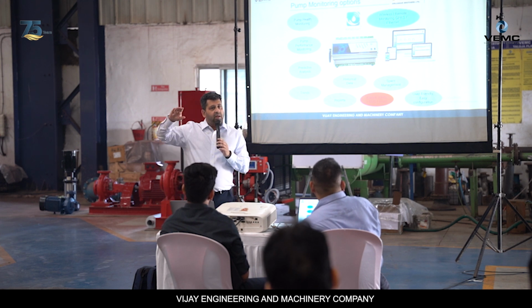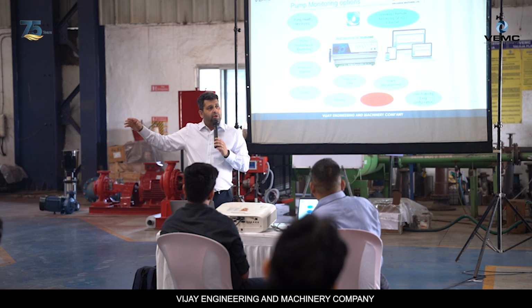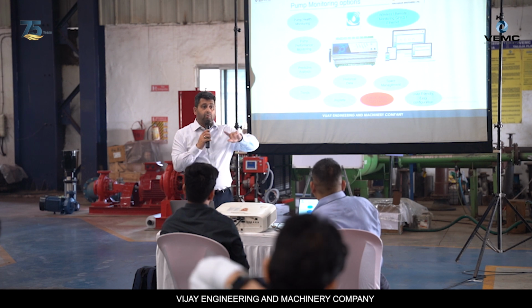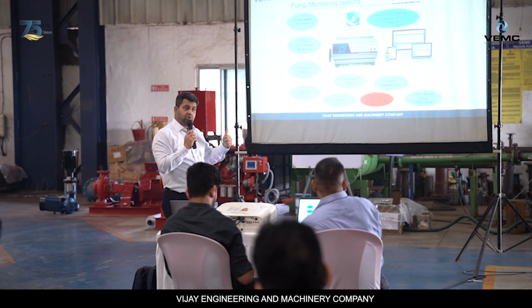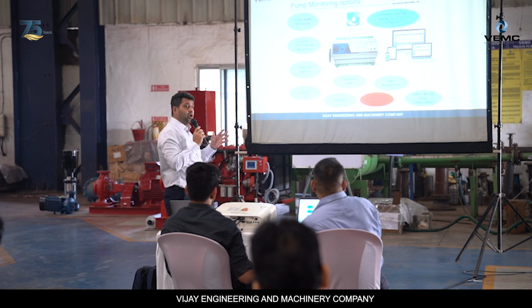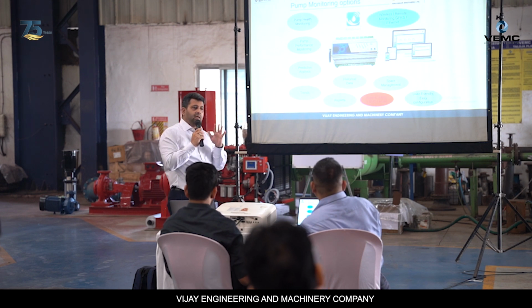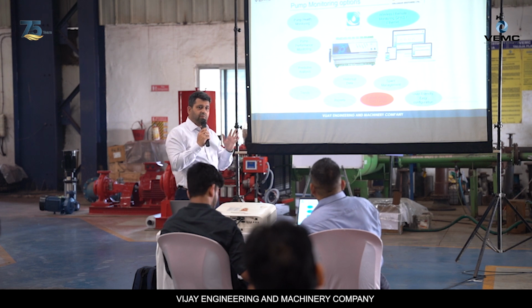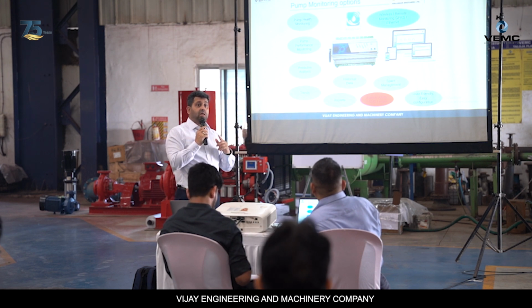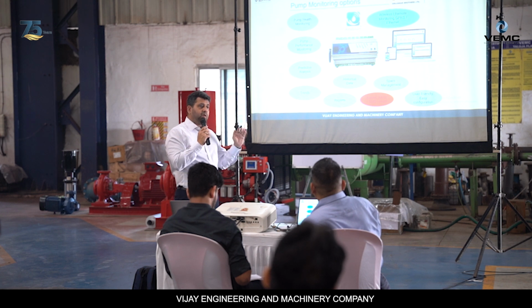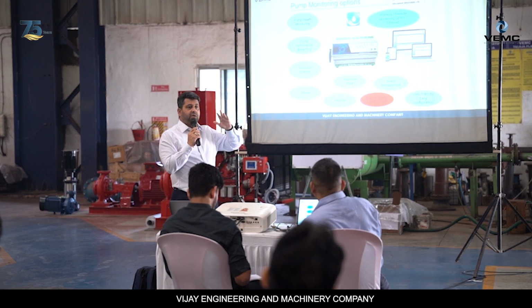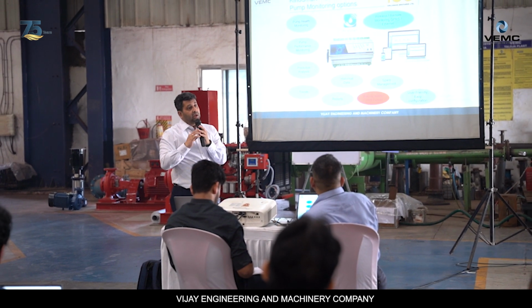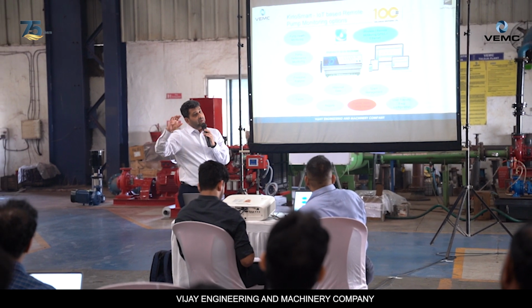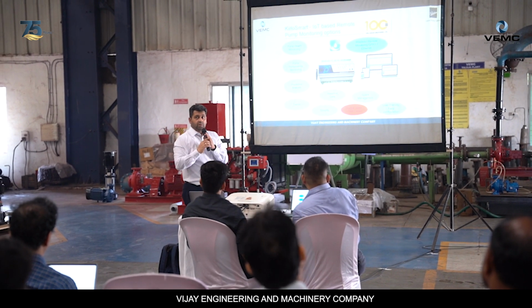You observe that over a period of time, the input of power is going very high, and this is something you can observe and say there could be a problem in the operation of the system. So trends give historical data. We gave one pump set to IIT Mumbai for their systems, and we had continuous monitoring for their multiple hostel buildings, and we observed the trend of how they were operating their pumps, what time the basic flow was higher, since they had a VFD operated system, and when it was lower. We could tell them this is your optimized power input required, and how you could look at other plants as well.